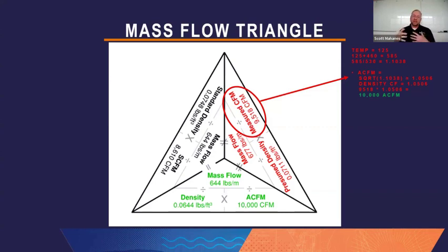Okay. And I would normally, as a technician, sort of stop there and say, okay, well, the design's 10,000, I'm measuring 10,000, and then my day is done. It's amps, volts, RPM, static pressure, closeout time. Because I have the targeted value that the design intent seemed to show. What I'm going to show you is this sort of paradigm shift of understanding that measuring volume accurately isn't always just good enough. You have to allocate what you measure correctly. And the only way for me to allocate what I measure here in this situation to what's really being moved by the fan is to actually turn it into a standard CFM value.